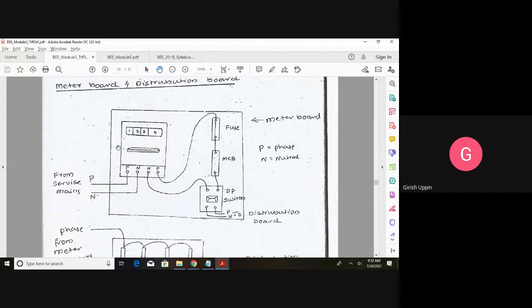So inside the meter board we have the energy meter. You can see it is the energy meter. This is phase and this is neutral, and it is connected to the energy meter. And from the energy meter, this is the phase connection that is connected to the fuse, and the fuse is connected to the MCB, and we have the switch, okay, double pole switch.